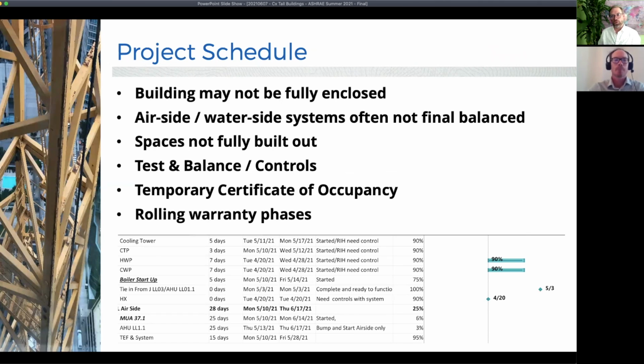So starting really with the schedule, tall building projects can go for years. They can be in design for several years and go into construction for several years. And I've worked on some projects that have taken 7 years from start to finish with our involvement in it to get there and then moving on. So there's a lot of moving parts though. And when it comes to commissioning specifically, some of the challenges that we come into with doing our work is that we might be doing some of the testing when the building's not fully enclosed. When you're working at height, you have a tower crane, you have skip units that go up the side of the building, and those often aren't taken down till fairly close to occupancy in a lot of buildings, and that can cause some issues when we come to testing things, especially on the air and pressurization side of the building. You really want the building to be fully enclosed before you do those commissioning procedures.